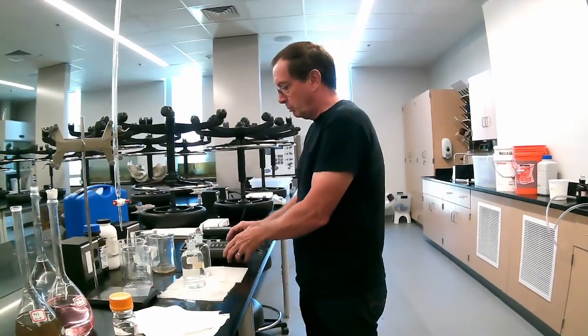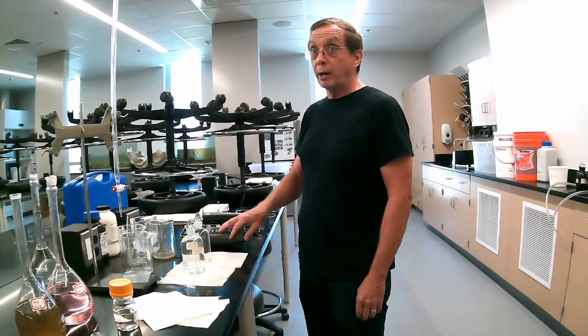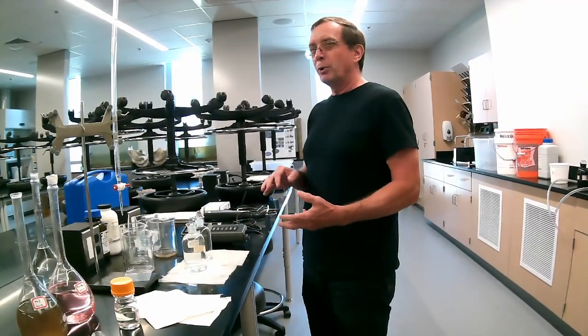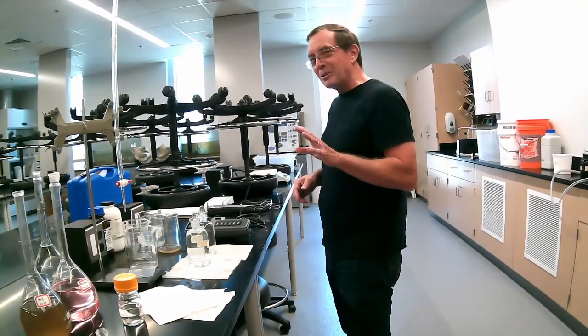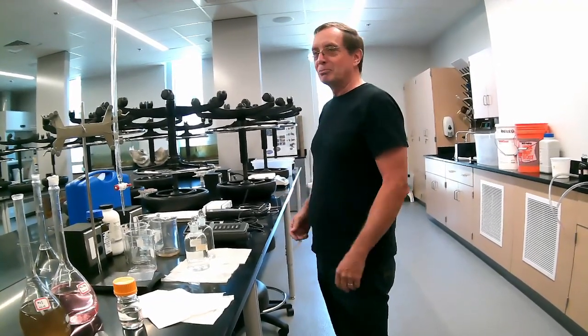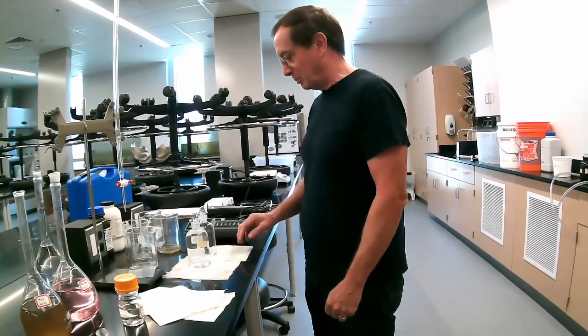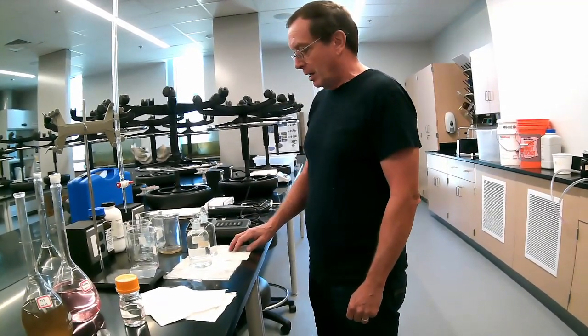I didn't mention, but with the YSI meters, usually when we turn them on, we let them sit for at least an hour before we use them. And so they're not as convenient as just flipping a switch, but if you forget to turn it on, you just go sit down and, I don't know, have lunch or whatever, and then come back when it's warmed up.